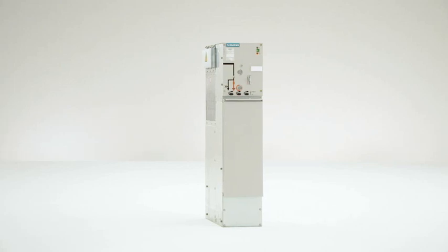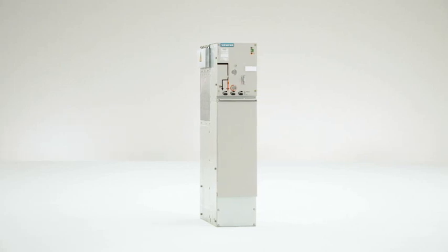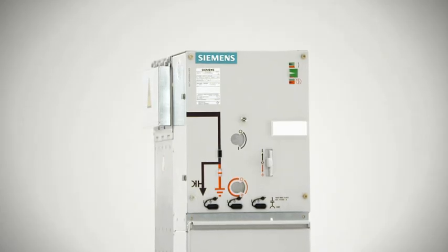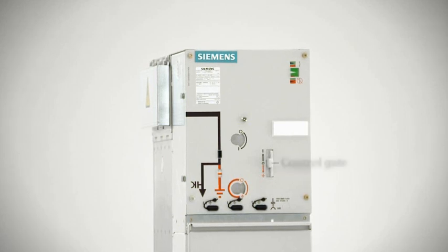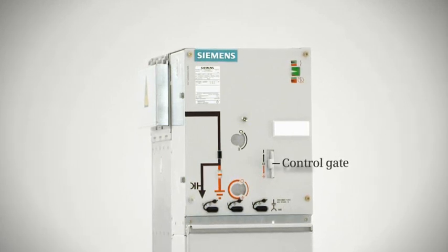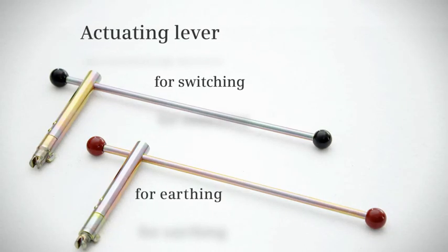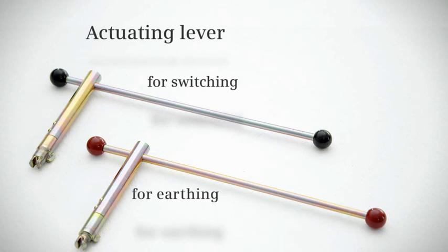The switchgear is based on the five safety rules for working on electrical equipment. Operating an 8DJH ring main panel, for example, is very simple. A control gate unlocks the actuating openings for switching or earthing. The switching operation is then carried out using the appropriate operating lever for each process.